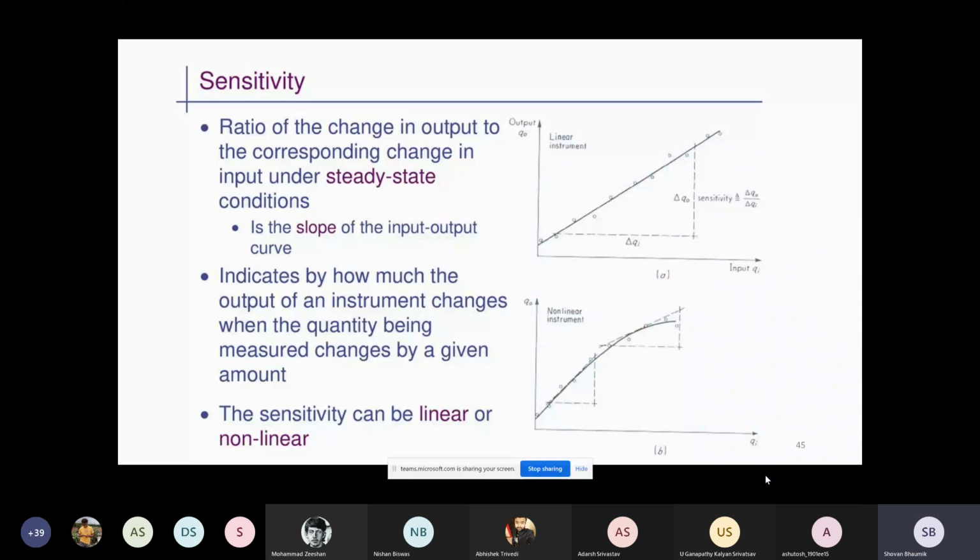So for increasing sensitivity, we need to increase the bulb volume, and bulb volume means the mercury quantity will increase, it will take more heat, and the measurement medium temperature will go down. That is not desirable. That is one part.